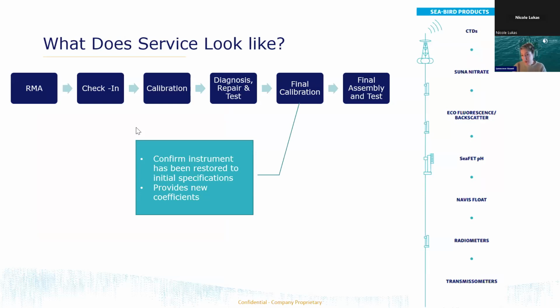After that, it's one more trip through calibration. A lot of our equipment, once you open that pressure housing and make changes, whether soldering or just exposing boards to different air, that can be enough to change how our instruments perform in terms of accuracy. So depending on what instruments you've purchased, that final calibration is the final confirmation step that any repairs we've done are performing well and as expected, and this generates new coefficients that you'll use for your instrument going forward.